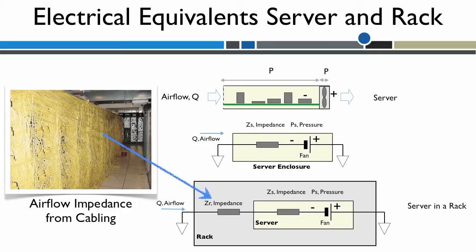The fan in the server has to overcome this additional impedance to deliver adequate air flow required to cool the server. If the additional impedance is high, the small fan may not be able to deliver enough air flow and this can lead to overheating of the server.